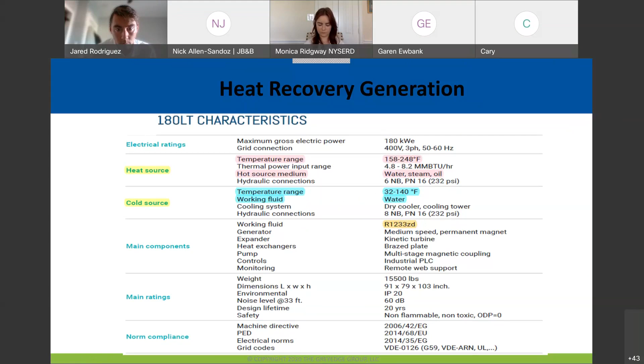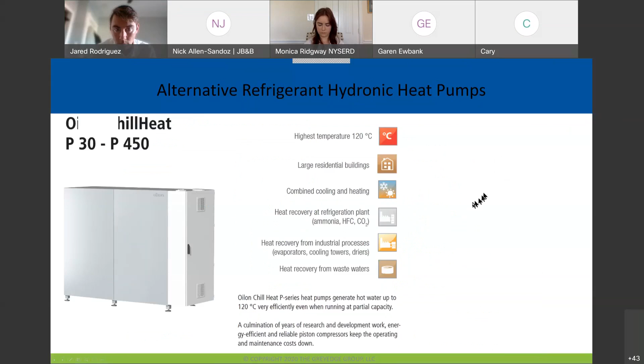I wanted to show this alternate refrigerant hydronic heat pump system, which actually changes the refrigerant based on the application. Here are the different refrigerants we can look at. We've got, for lower temperature, 134A. As we move up, some of these refrigerants expand the maximum temperature we can use on the system. So if all we're doing is taking care of Legionella, we need to heat to 145 to 160. We might use one refrigerant, and that gives us a curve showing efficiency we can recover. With another refrigerant, we could bump it with a smaller unit. This has typically been done all the way up to 185 degrees with 134A, which is a very common refrigerant in the United States.